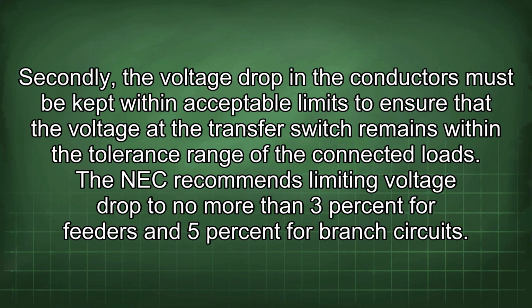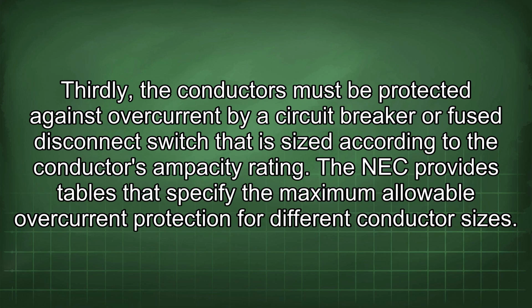The NEC recommends limiting voltage drop to no more than 3% for feeders and 5% for branch circuits. Thirdly, the conductors must be protected against overcurrent by a circuit breaker or fused disconnect switch that is sized according to the conductor's ampacity rating. The NEC provides tables that specify the maximum allowable overcurrent protection for different conductor sizes.